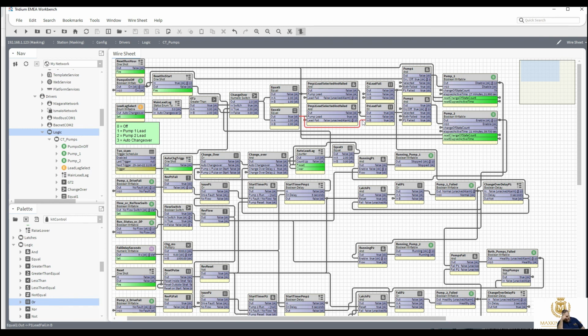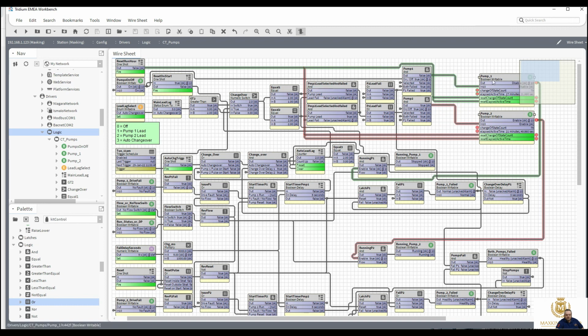There was something else I was thinking of when I was just writing that. What would be nice to have? Yes, it was an on and off delay for the pumps. If this was a boiler pump, 2 boiler pump control, when we turn it off, we really want the pumps to run on a bit longer to clear the heat exchanger for boilers. So I would say 5 minutes, 10 minutes, but sometimes you don't need them to run on at all.